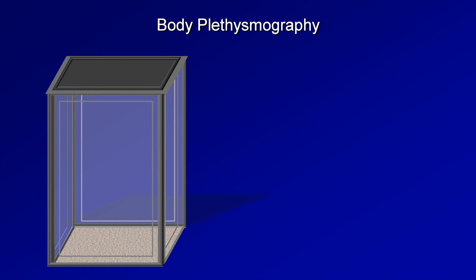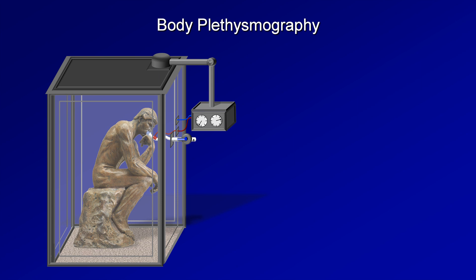Body plethysmography works on a completely different principle. It starts with a clear plastic or glass box the size of a phone booth. There is a mouthpiece inside and a tube to the outside air. Attached to this tube, outside of the box, is a stopcock or other type of closeable valve. Then there are pressure transducers which record the pressure within the airflow tube and within the box itself. The patient sits inside the box, quickly panting with the airway open when it is suddenly shut while the patient continues to pant. This creates oscillations in the airway and box pressures.